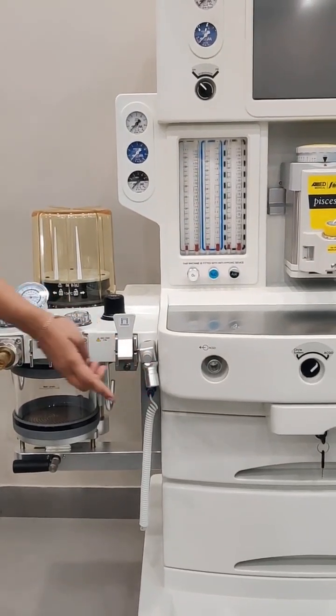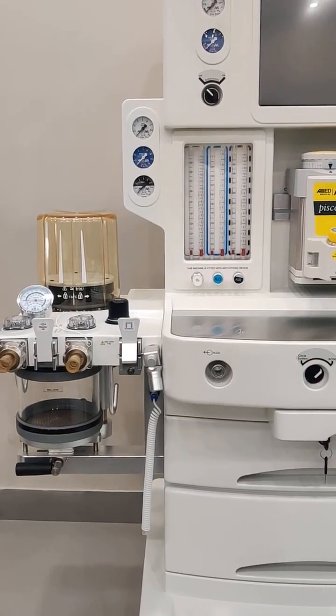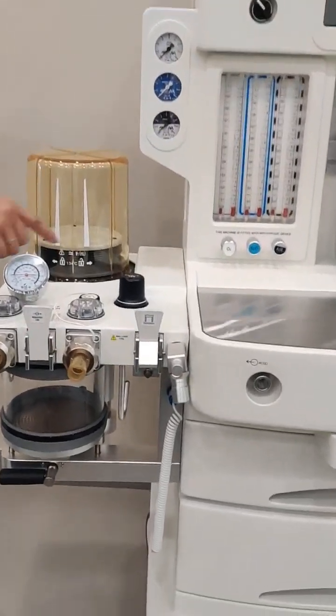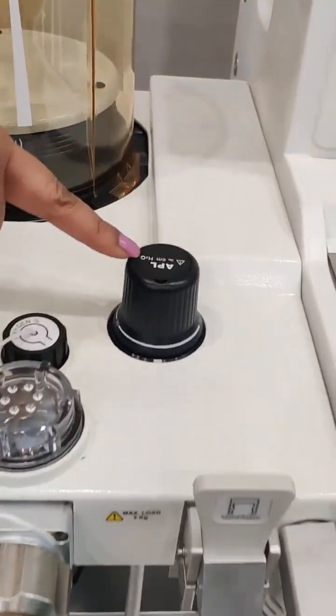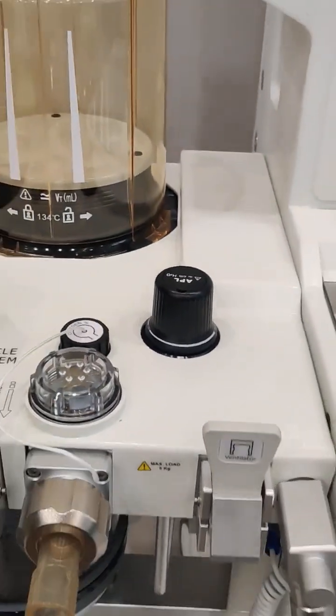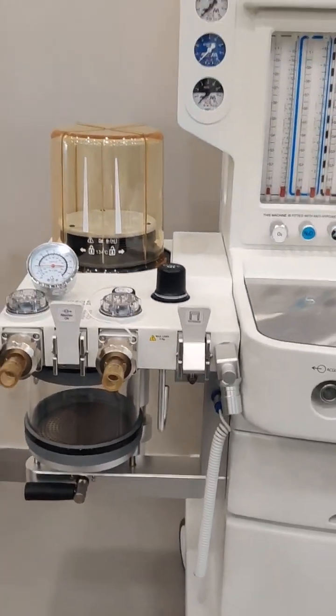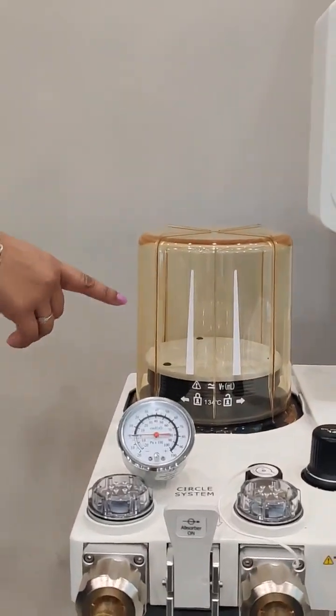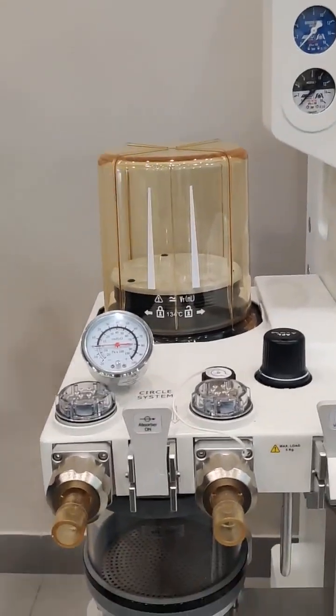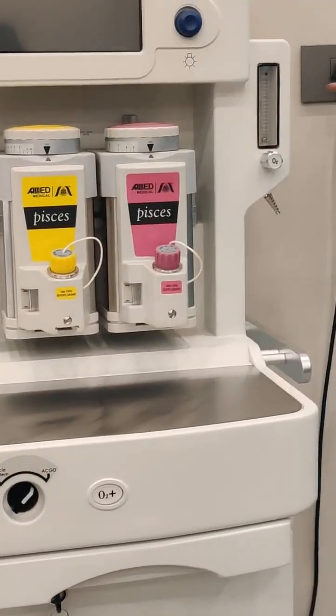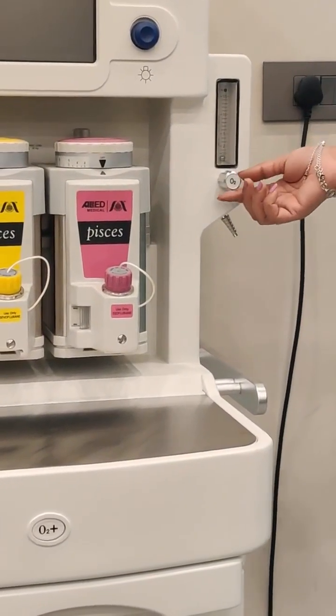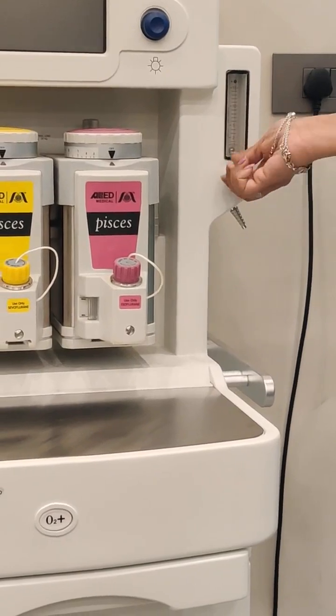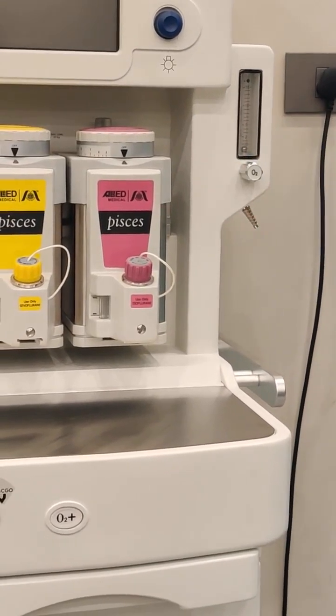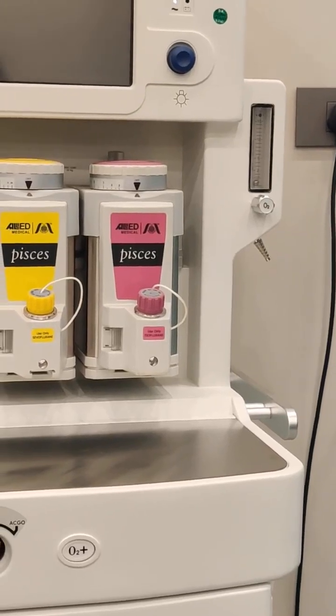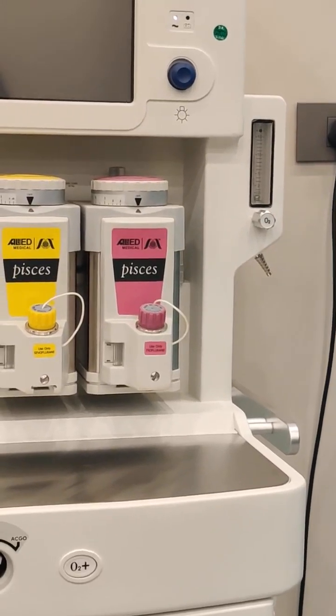Here you can connect the breathing bag for manual ventilation, and the APL valve is available, which is a calibrated APL valve with gradings on it. The same bellows system can be used for adult and pediatric mode. The machine is also equipped with an auxiliary flow meter with a dedicated knob and a dedicated nozzle, where you can connect the venti mask and control the oxygen. Even if the machine is turned off, you can use this auxiliary flow meter.